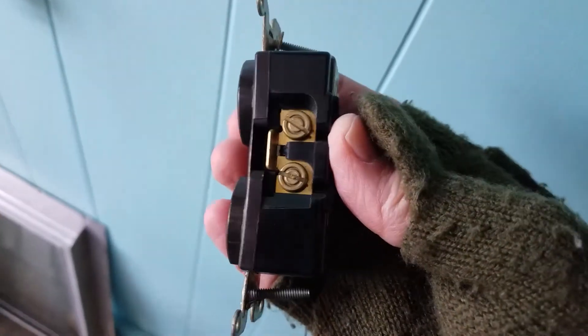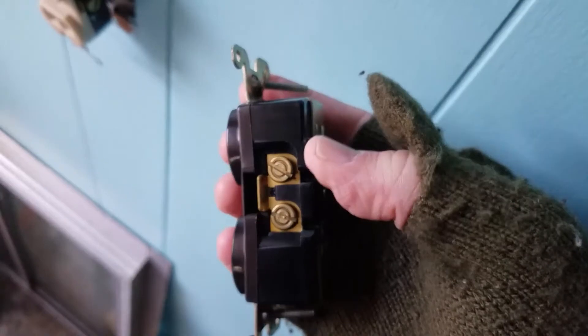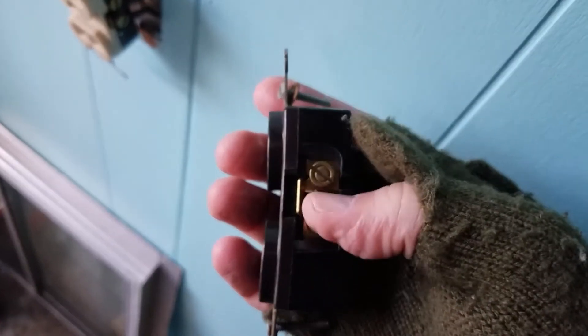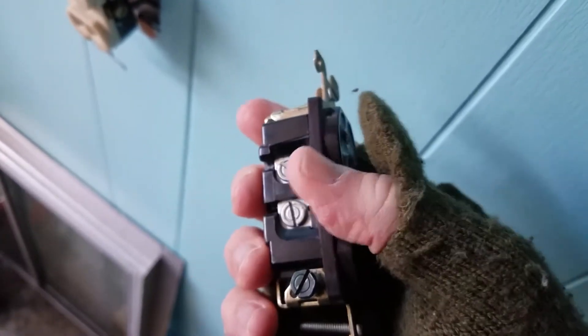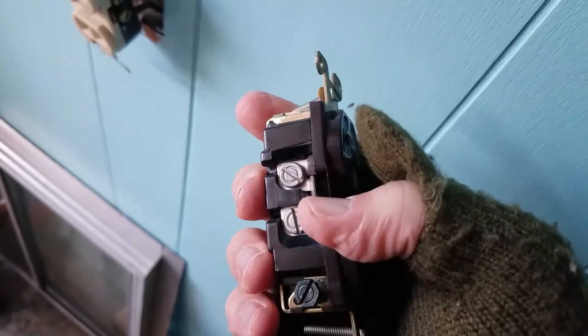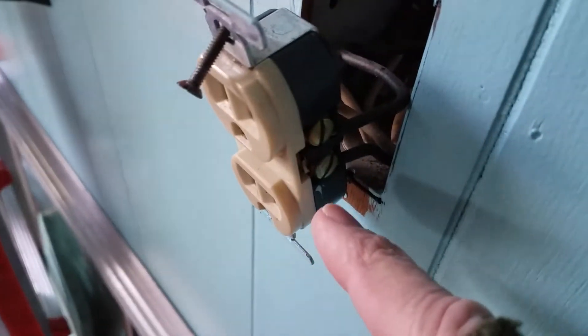For those of you who want to know how to install this, the brass looking contacts take the black leads, that's the load side. And the white or silver side is the neutral side, which is your white cables.